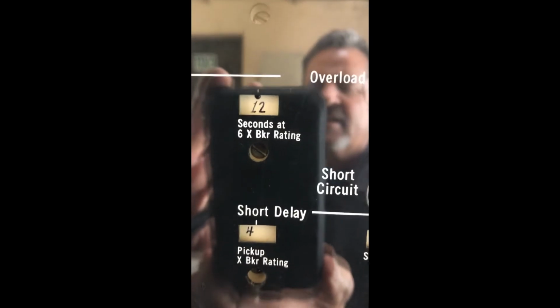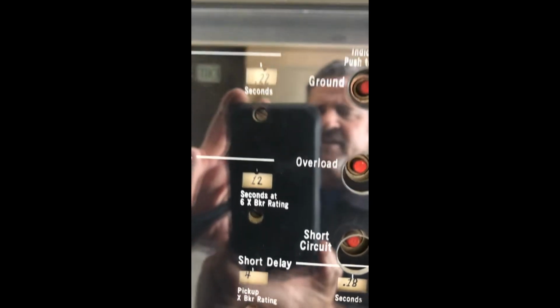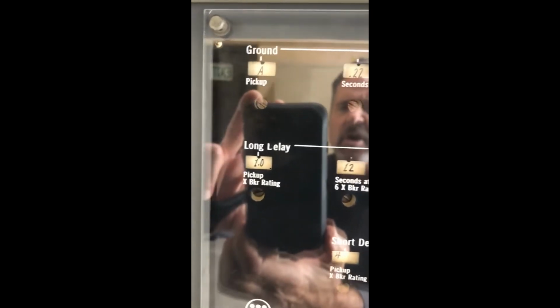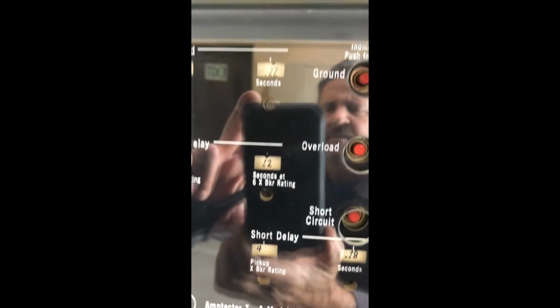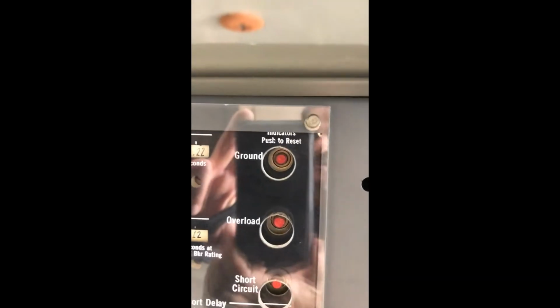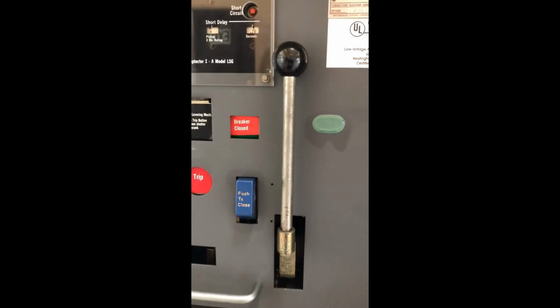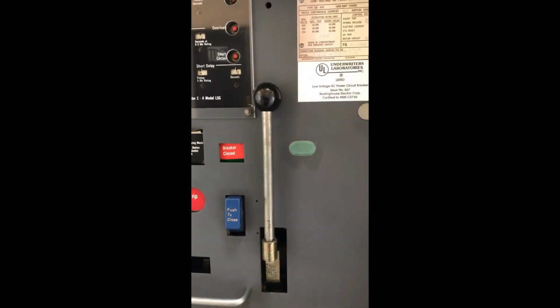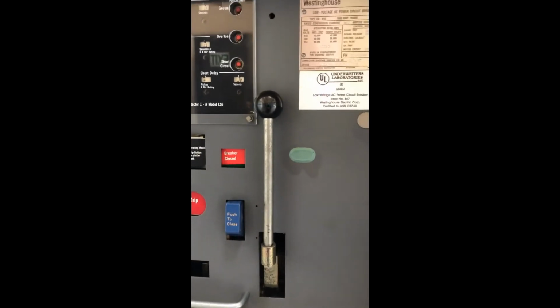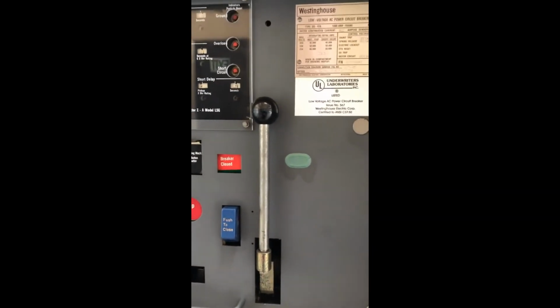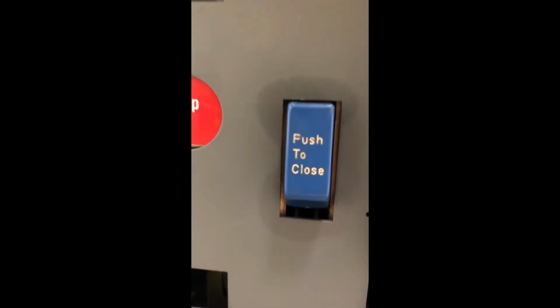We have the short delay, the long delay, and also the time settings as well. With these large breakers, when you have to recharge them, there's a handle here. You got to pump them up. You'll know when they're fully charged because the handle will get real easy to move, and then you operate this push to close button. That's how you operate these breakers.